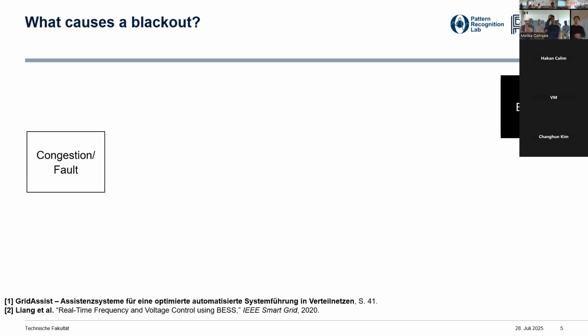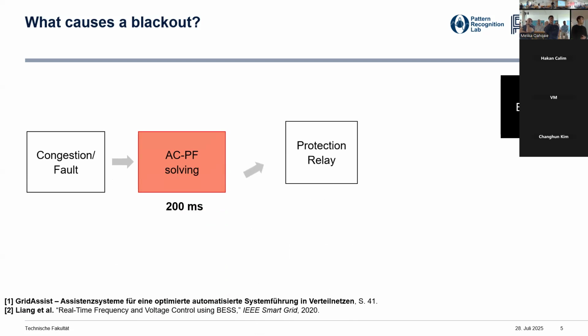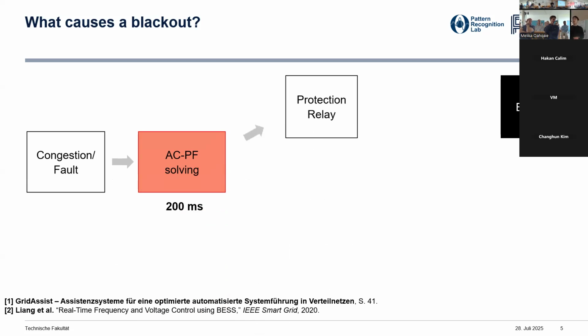So what actually causes a blackout? Whenever congestion or a fault happens in a specific region in the grid, to detect the voltage violation we always need to calculate the AC power flow within a few hundred milliseconds. Otherwise, the protection relay may activate, potentially leading to a cascade trip, which can lead to a large-scale blackout.